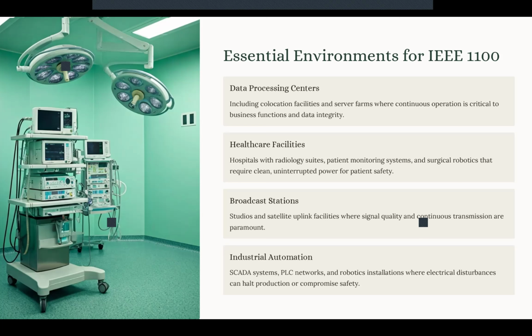Another environment is industrial automation, like SCADA systems, PLC networks, and robotic installation control. Those systems control entire production lines or any distribution system, and any variation or disturbance leads to production downtime or a safety hazard. So, for example, we need load segregation and zone design. We are going to talk about that. Grounding and signal integrity is very important. And when we talk about safety, surge and harmonic control also become a very critical aspect of these recommendations by IEEE 1100.